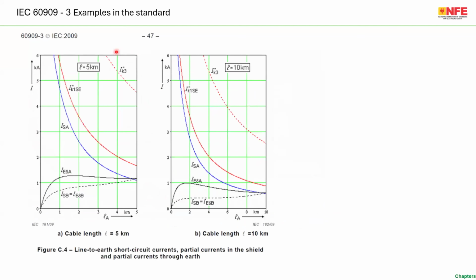If you go through the annexures, you will be able to find the examples. Say, for example, if you have a cable length of 5 kilometers, how much current is going to flow through the shield? How much IE, meaning how much current, is flowing through the earth electrode? With 10 kilometers between station A and B, how much current is going through the earth electrode, and how much through the shield wire? All these are very well explained.